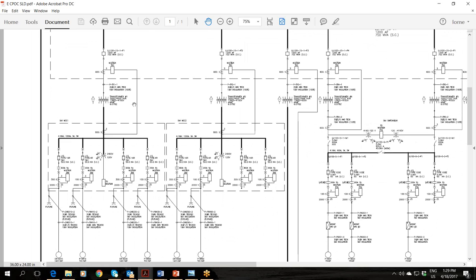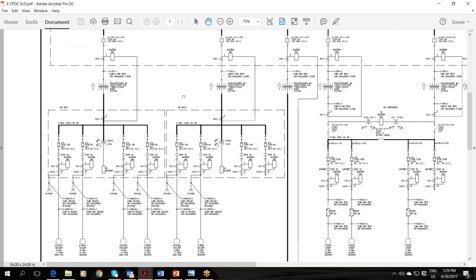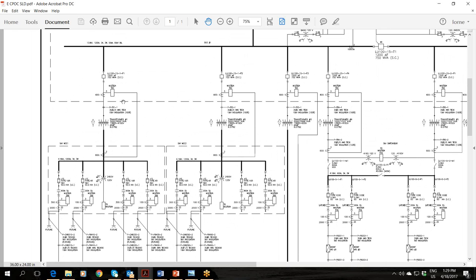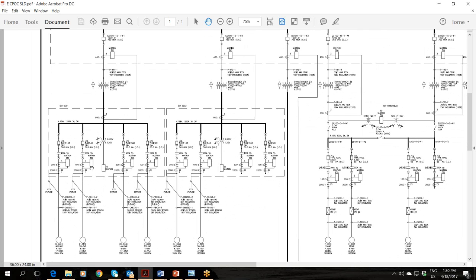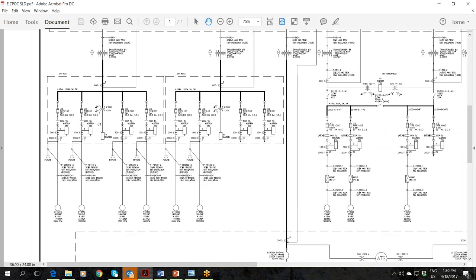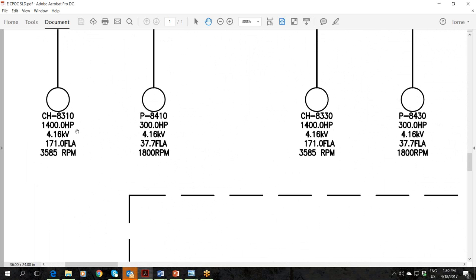From that 15 kV switchgear lineup, we go down to some step-down transformers. Again, dry type, cast coil. We standardized on cast coil, not so much because we have very harsh environments, but oftentimes our transformer infrastructure is in the basement of buildings, and in case there is some kind of sprinkler system or flooding in that basement, these things, being cast coil, are quite rugged in terms of the environment they can be put into. So we've decided that we'll pay the additional percentage fee. I think it's around 15% to get cast coil for that ruggedness and that longevity. So anyway, step-down transformers, then it goes to 4160 volt here to feed some of the larger motors.